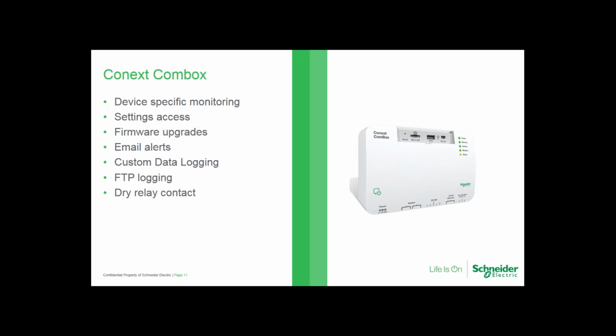Firmware upgrades are an important benefit because it's always the best practice to have the latest firmware in all the devices. Just because a unit is new in the box does not guarantee it has the latest and greatest. Emails can be sent to report production and faults. Custom data logging is an invaluable tool in diagnosis of unusual behavior. File transfer protocol is just another means of logging specific data that may be useful. Finally, the dry relay contact can be set to trigger an alarm if a fault occurs.